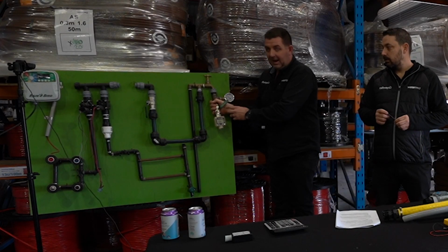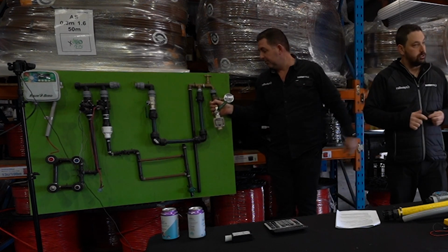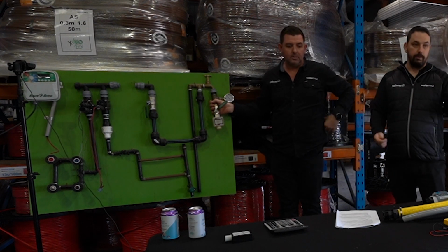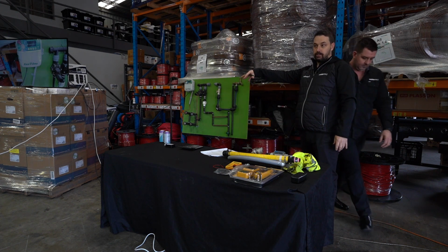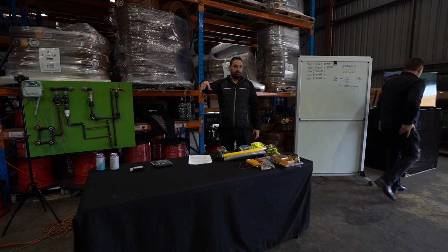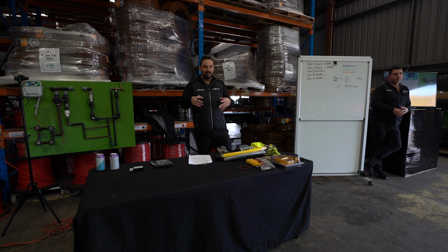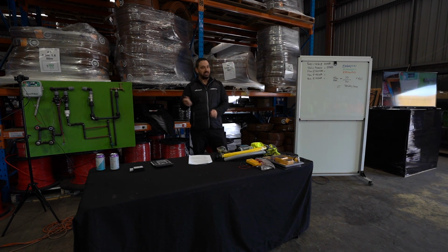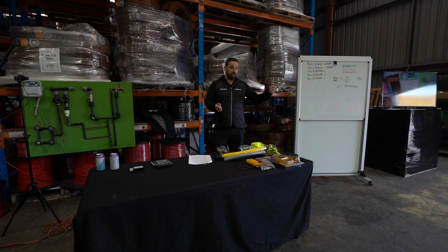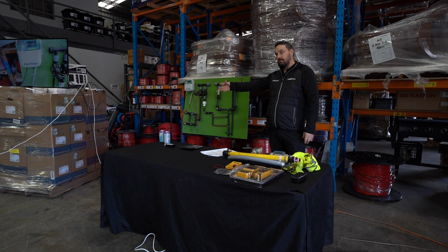What I'm doing now is just adjusting the handle until I get a point on the gauge that I'm happy with, to try and meet those points. So APG as an example, obviously we did one out at Galway for the guys. There was just a water meter given there, and we were involved in the irrigation design, so I wanted to make sure, before the water meter was there, we already did the design, because a lot of the time you're designing ahead of housing networks getting in. Now that it comes to the construction phase, we want to make sure that what we've designed is actually going to work. So we'll get engaged by the client at times to go out there and actually test the flow and the pressure, and then we'll cross-check that back against our system to make sure that it works.